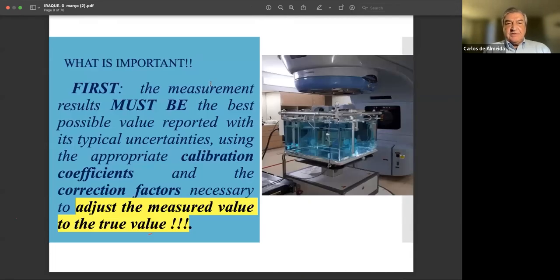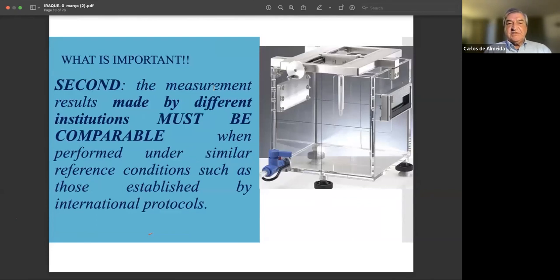What is important is that what we measure must be the best value possible, most carefully done, and we should use calibration coefficients and correction factors to adjust the measured value to the true value. So there are several steps involved when you are measuring in a particular situation, either in air or in a water phantom. Second, the measurement results made by different institutions must be comparable. In other words, you in Iraq should measure the gray the same way that I measure in Brazil.